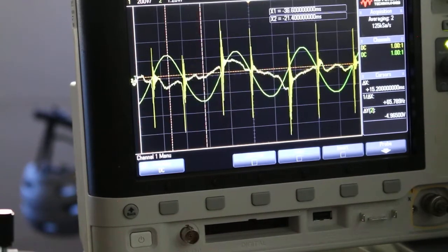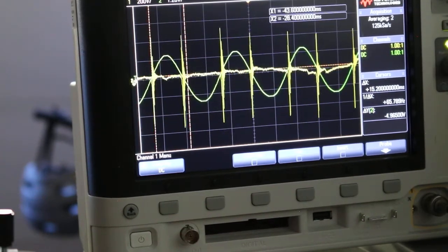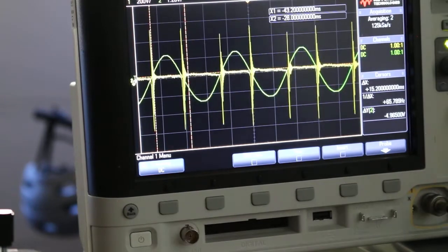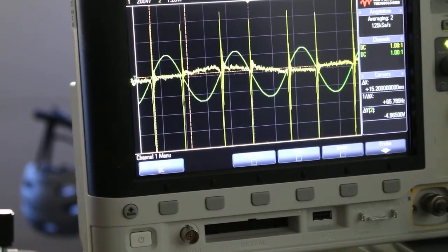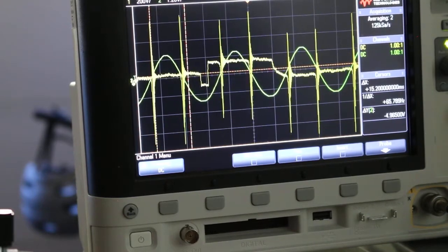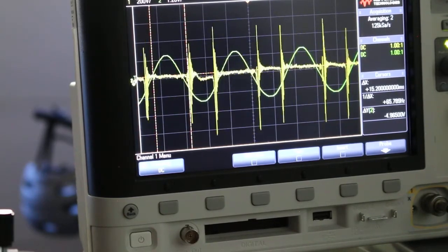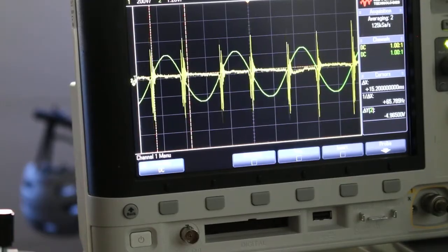That's fine, but I still say the core cutoff here is whether these resonances are equally spaced. I see it has drifted quite a bit just while I'm talking to you, and that's what makes this kind of difficult. Let me bring them back. I have my hand on the amplitude knob at the moment, so I'll realign it. But that's a tour of how data is taken.